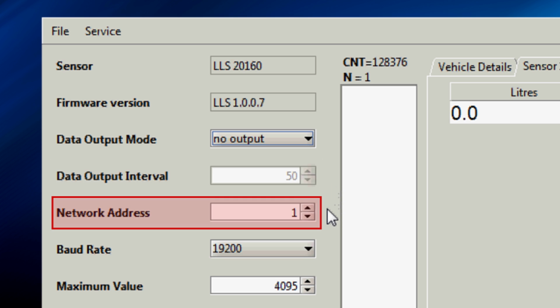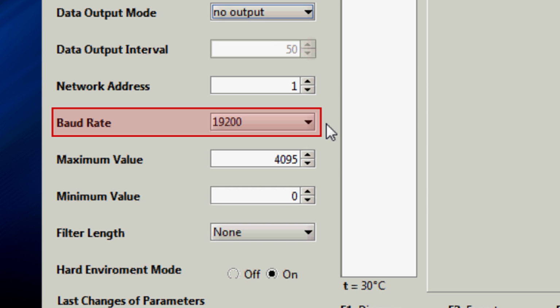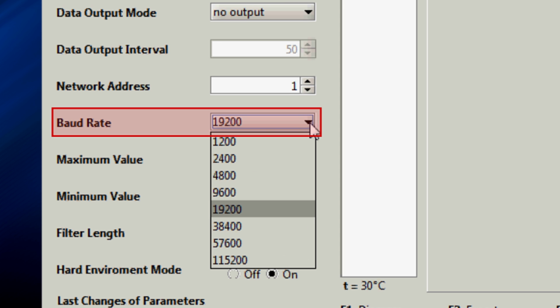The next setting, network address, is important for every sensor. If only one sensor is connected to the onboard terminal, you have to specify the address as 1. If there are several sensors, their network addresses must be both unique and sequential: 1, 2, 3, 4. If the Omnicomm sensor is integrated into a system of other vendors, you may have to configure the baud rate. The default data rate setting for Omnicomm terminals is 19,200 bits per second.